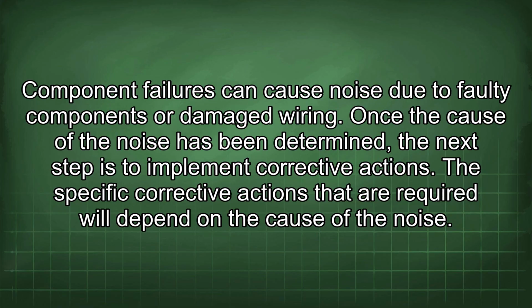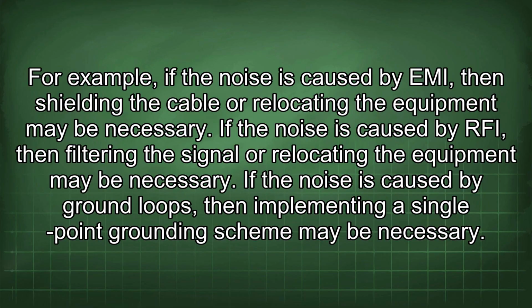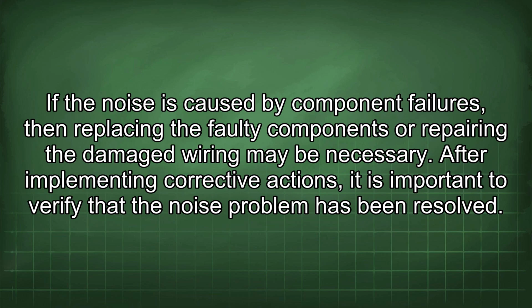The specific corrective actions that are required will depend on the cause of the noise. For example, if the noise is caused by EMI, then shielding the cable or relocating the equipment may be necessary. If the noise is caused by RFI, then filtering the signal or relocating the equipment may be necessary. If the noise is caused by ground loops, then implementing a single-point grounding scheme may be necessary. If the noise is caused by component failures, then replacing the faulty components or repairing the damaged wiring may be necessary. After implementing corrective actions, it is important to verify that the noise problem has been resolved.